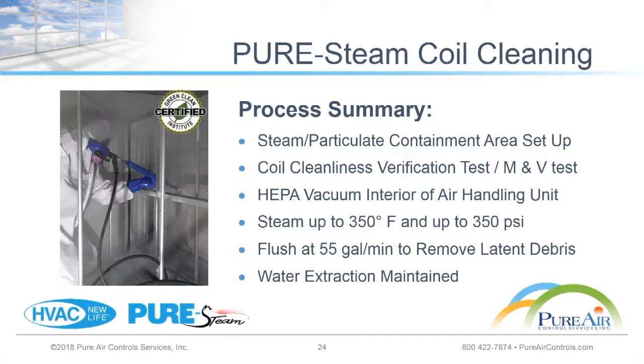So we're going to take that test, we're going to log it, and we know what the condition of the coil is in. Next, the entire unit, not just the coil, not just the pan, but the entire unit is HEPA vacuumed. That's going to get any particulate up, any rust, any of the loose dust that is on it. It's a wet-dry process, so if there's biofilm or anything like that, that will get vacuumed up as well.